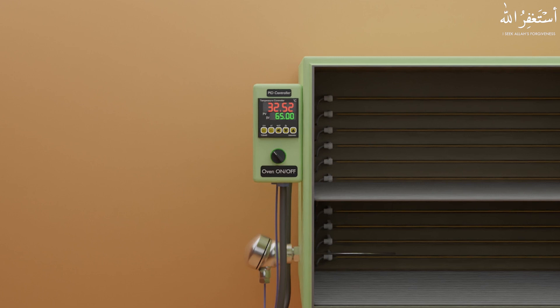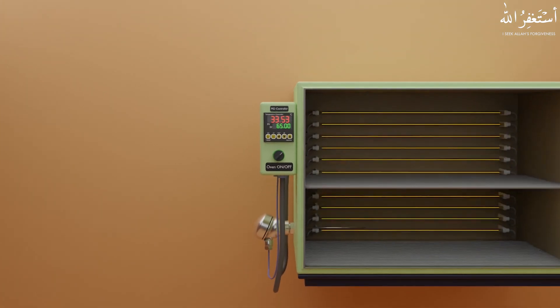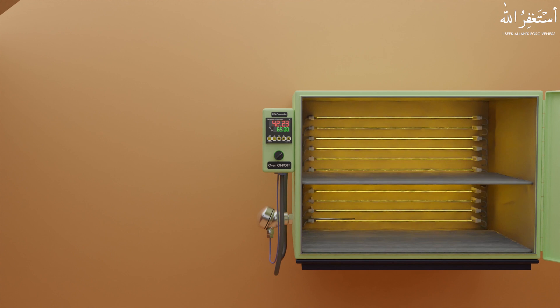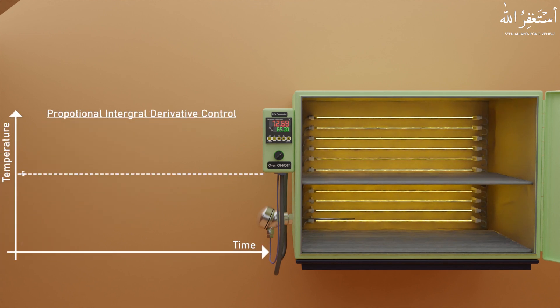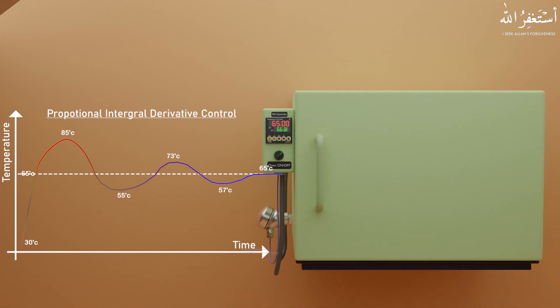As we start the process, the PID controller turns on the heater and starts regulating its power by sending a PID analog output signal to the power regulator circuit of the heater. The heater starts to heat the oven and slowly the temperature rises. As you can see, the temperature rises and falls below the setpoint a few times, but every time it reduces the difference between the setpoint temperature and the actual temperature. Eventually the temperature stabilizes at 65 degrees, and the PID controller is now constantly taking feedback from the thermocouple and regulating the heater power to maintain that temperature.